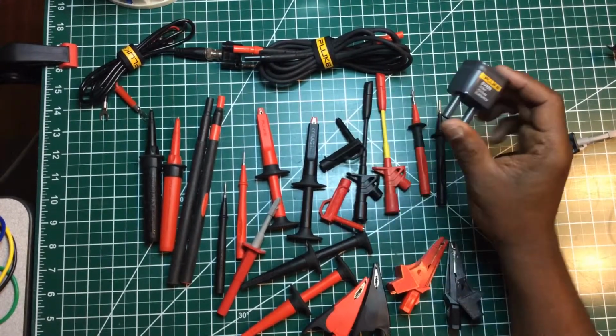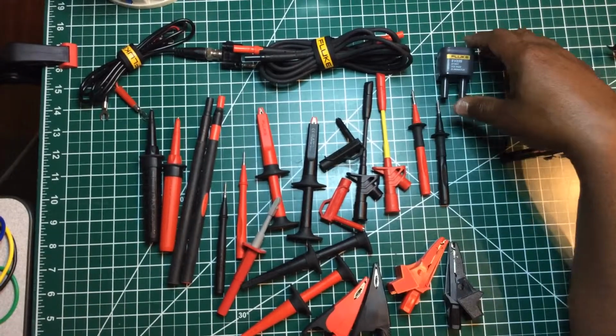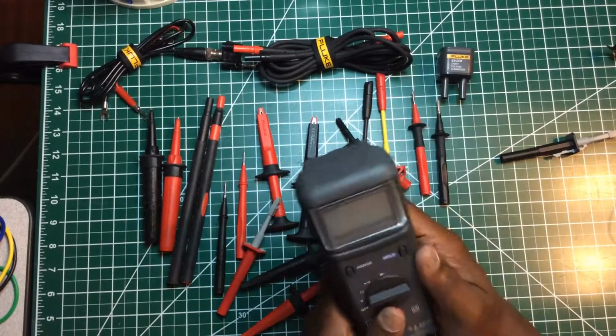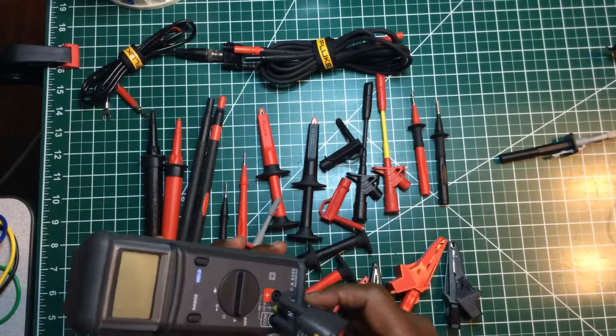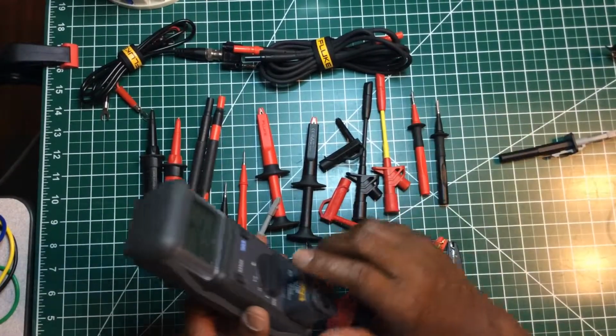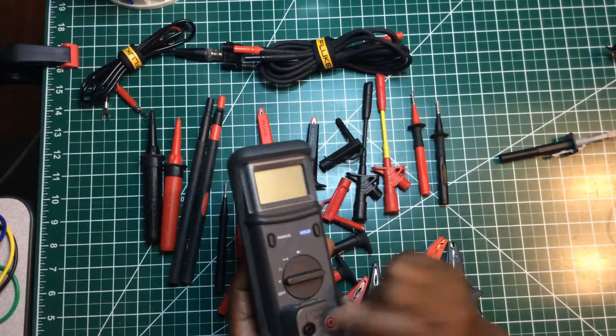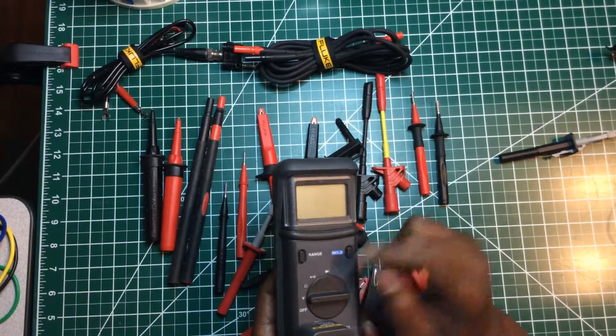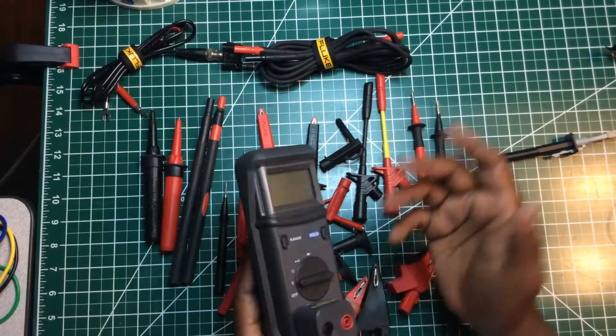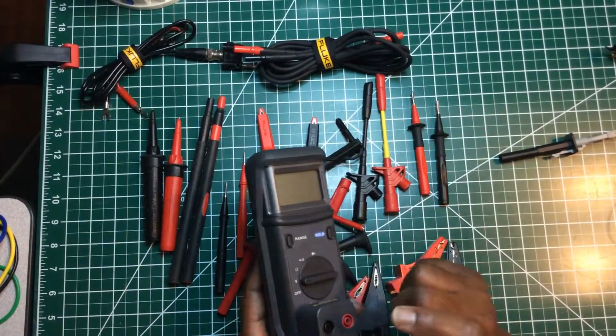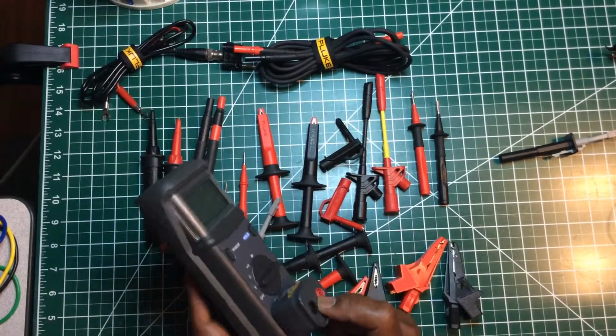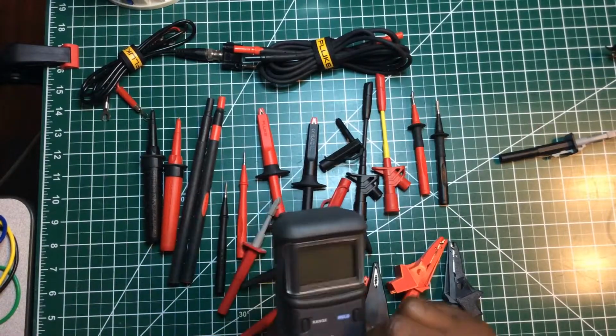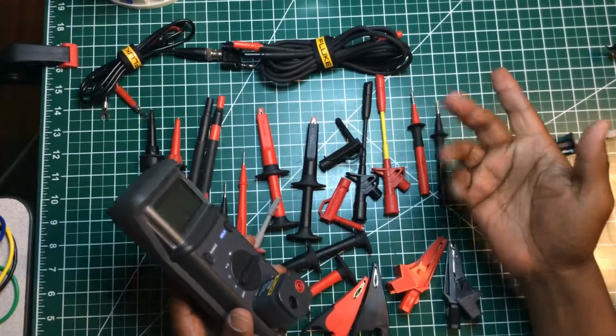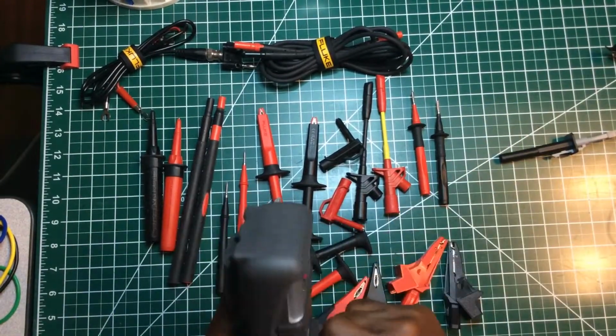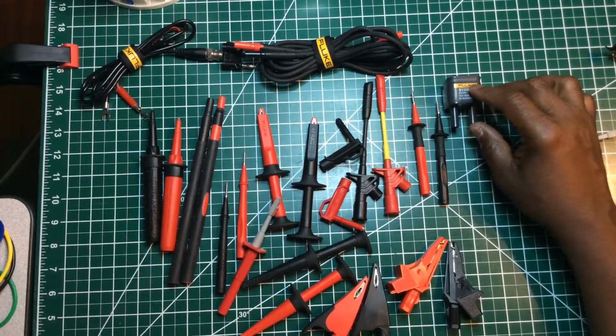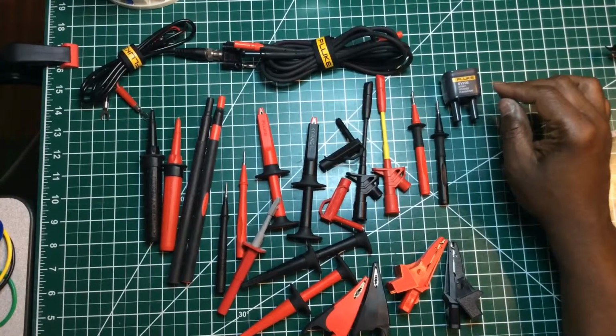This is called the SV225 Static Voltage Eliminator. What it does is, if you have a multimeter, let's say this AEMC CA5205, it doesn't have low Z, but if I plug this adapter in and try to take a reading, I just gave this multimeter a feature it didn't have, which is searching for ghost voltage, the real terminology being low Z. It just adds that feature by putting this Fluke adapter into the multimeter. I put it on volts, plug my leads in, and take a reading, and there you go. So I always put this on there. I have a 376 Fluke clamp meter that doesn't have low Z, and I normally keep this on the bottom of it when taking tests. You never can be too careful.